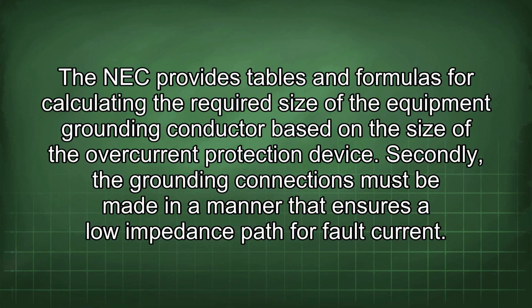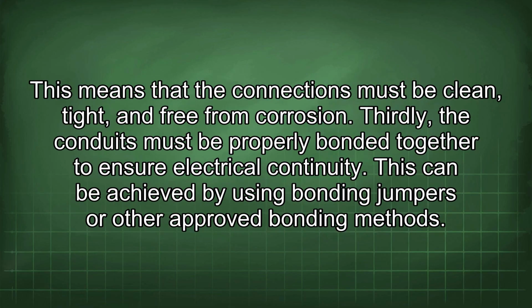Secondly, the grounding connections must be made in a manner that ensures a low impedance path for fault current. This means that the connections must be clean, tight, and free from corrosion. Thirdly, the conduits must be properly bonded together to ensure electrical continuity. This can be achieved by using bonding jumpers or other approved bonding methods.